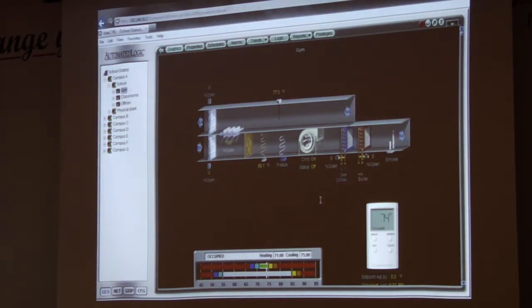And this happens once in a great while, where you say, you know what? I know the screen says the command is on and status is off, but I was just by the unit. I could feel the air. It's running, right? So right off the bat, we know one thing, right? Current sensor could be broken, right? Okay, great. We know another thing. We need our valves to open.